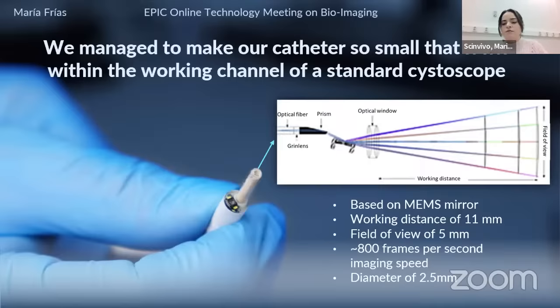We have a field of view of 5 millimeters and a working distance of maximum 11 millimeters. This working distance of 11 millimeters means we can be around 1 centimeter away from the wall of the bladder, and we can still scan it and go in depth. This is very convenient because, as you can imagine, it means very reduced harm for the patient. We don't touch the tissue, so we don't create any extra lesions.